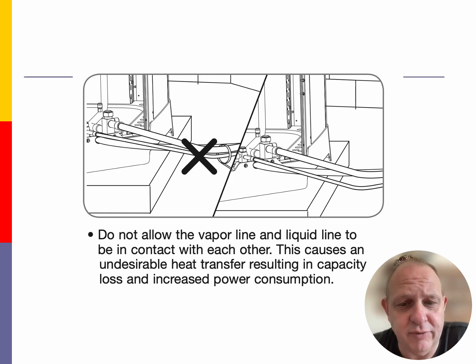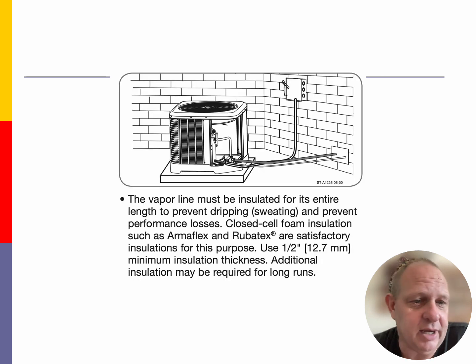The vapor line must be insulated on this system. Mini splits are different, like I said before, where both lines are on the low side of your system. Both of those lines need to be insulated, but the vapor line on a split type traditional air conditioner needs to be insulated because it's going to be a foam type of insulation that's going to prevent the moisture from getting in and causing condensation.